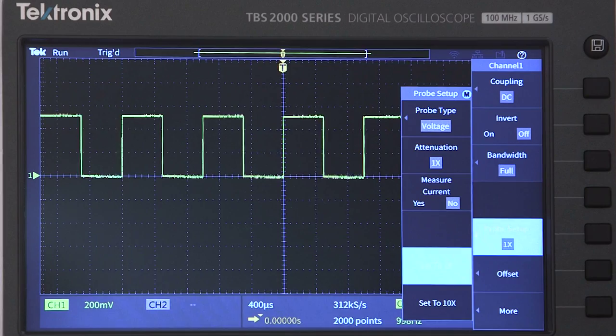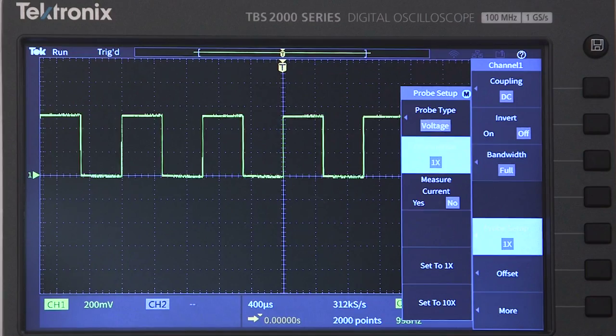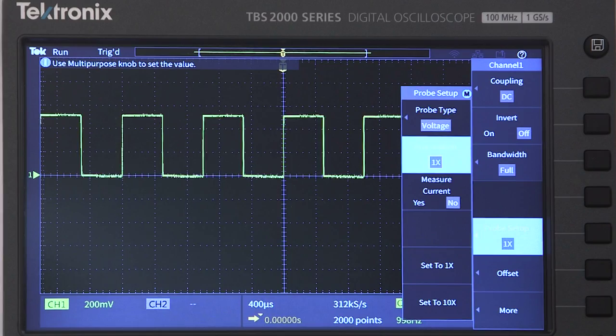Most of the time, you'll be measuring voltage waveforms, but in some cases, you may want to measure current. In these situations, you can set the probe type to current, and the scope will display amps instead of volts.